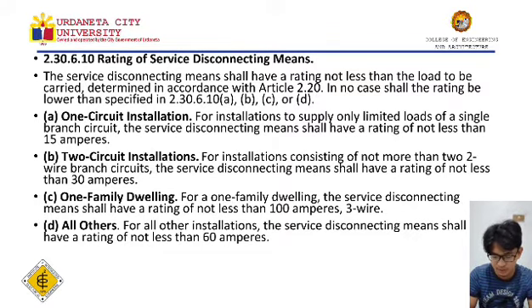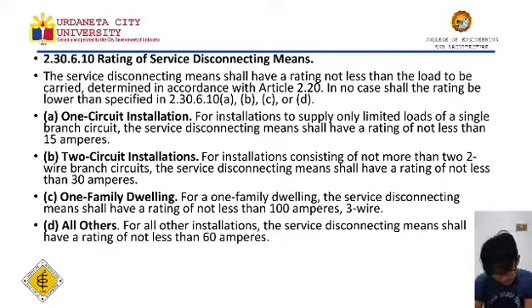So, sa next naman po is one family dwelling. For a one family dwelling, the service disconnecting means shall have a rating of not less than 100 amperes, 3 wires. So, one family po, ang one family dwelling ay para sa tirahan ng isang pamilya. Ang disconnecting means ng service nito ay hindi baba sa 100 amperes 3 wire.